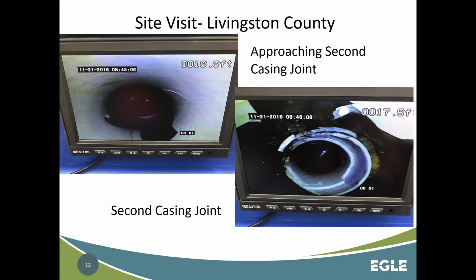This well was in a really difficult location to replace as well. So we ended up coming out with a downhole camera, and we were hoping that maybe the top joint or a piece real close to the top had fractured. You can see we got down to a point here at about 16, 17 feet, and you can see that the entire bell and spigot portion of the casing, you can see the inner and the outer where they were glued together here, completely exploded.